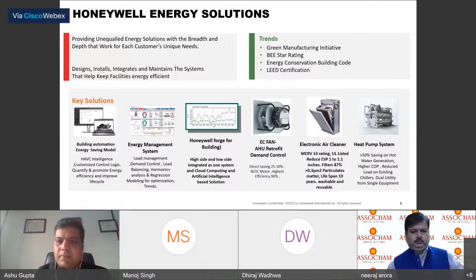Now the electronic air cleaner is also a very important solution people should think about, and we've already implemented a lot of such solutions. As per guidelines, MERV 14 rating is required in buildings for better filtration. Honeywell offers an electronic air cleaner, which has very low static pressure drop across filters and can give you performance as good as MERV 14. So all mechanical type filters can be replaced with electronic air cleaners to lower static pressure drop and increase CFM. Once your CFM increases, you can reduce frequency on the blower to get the same impact. This is another important idea for hotels and hospitals.